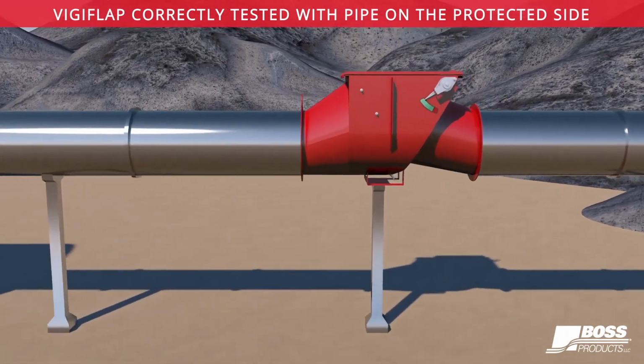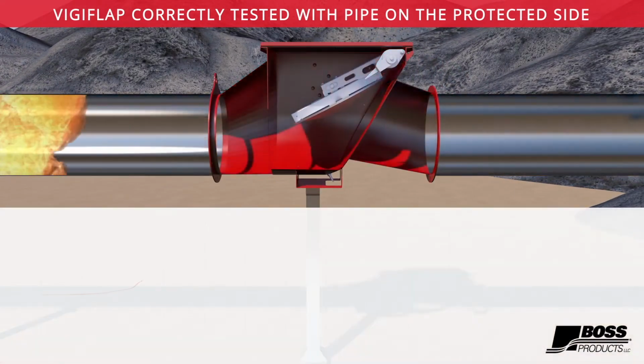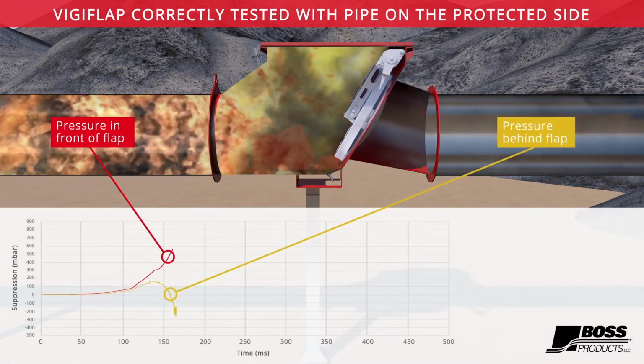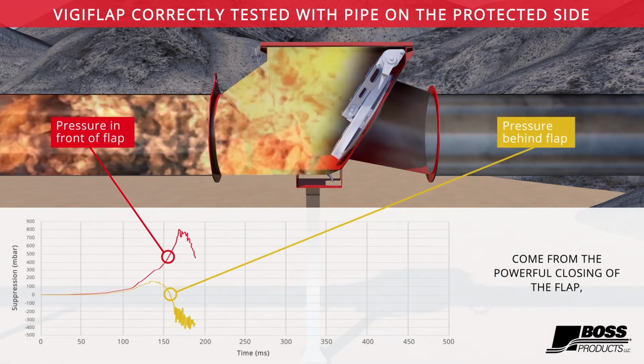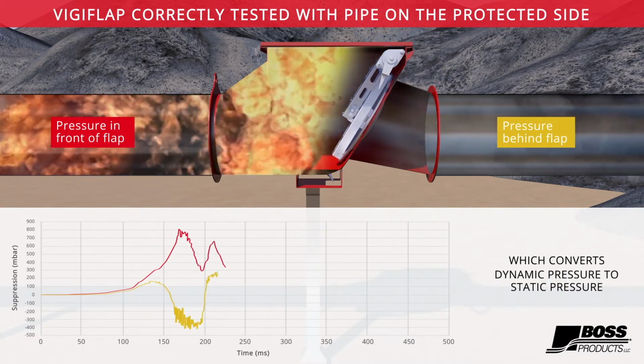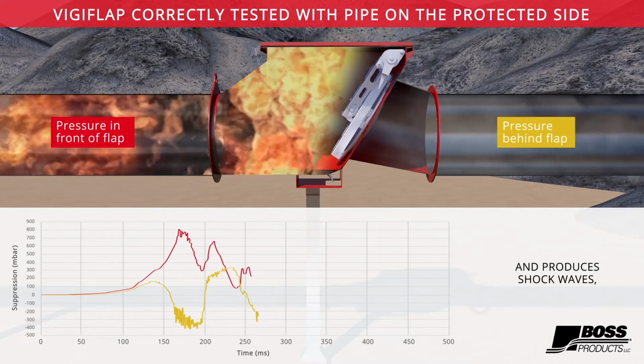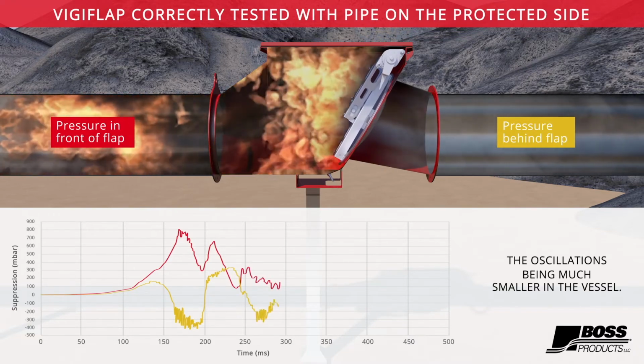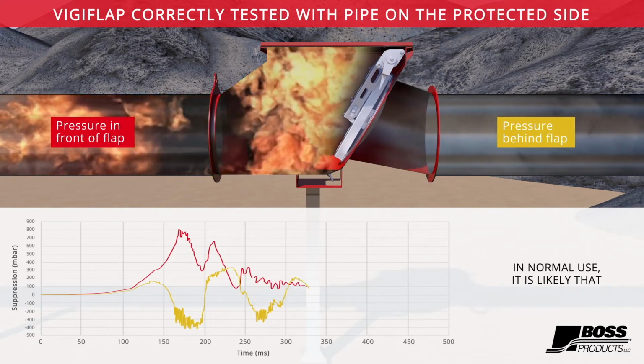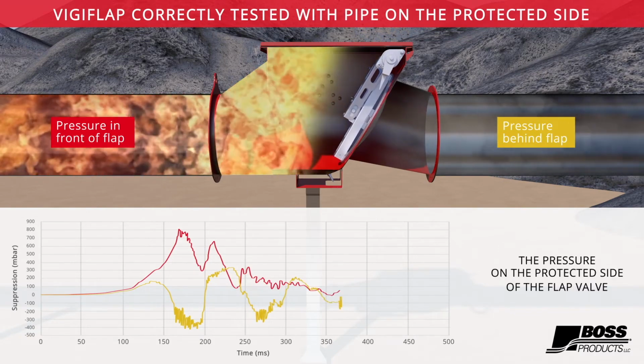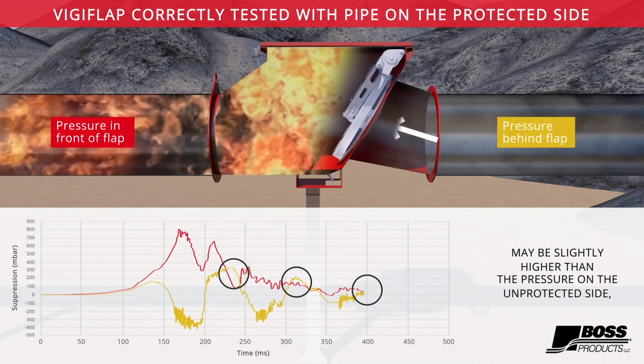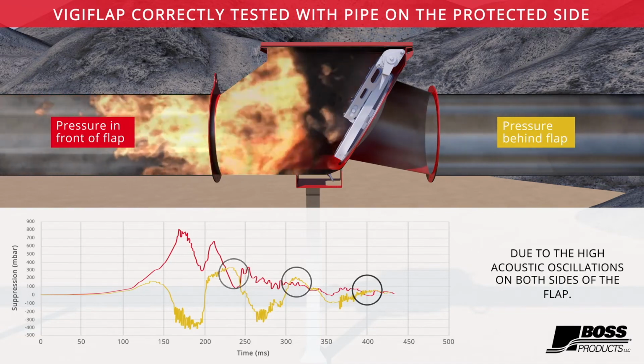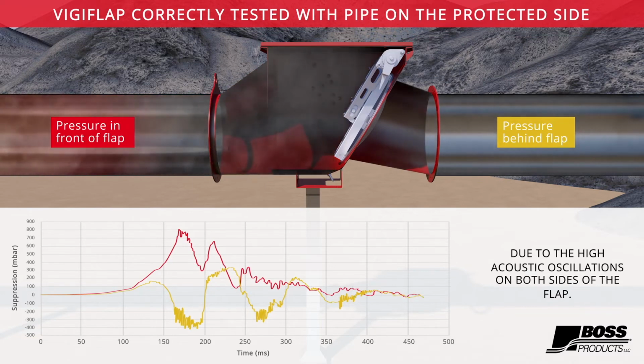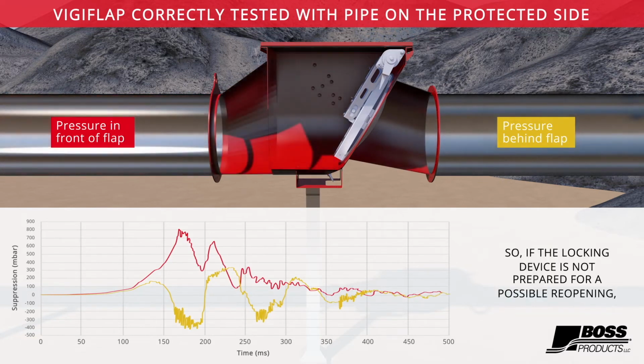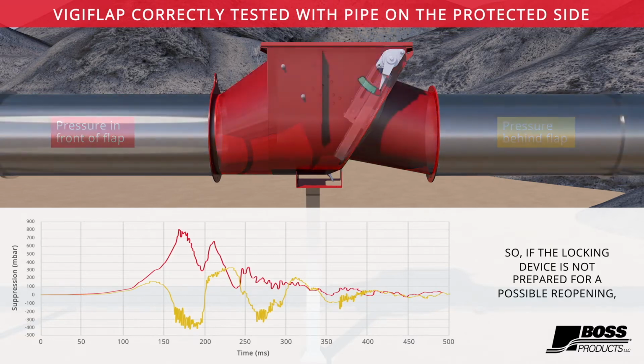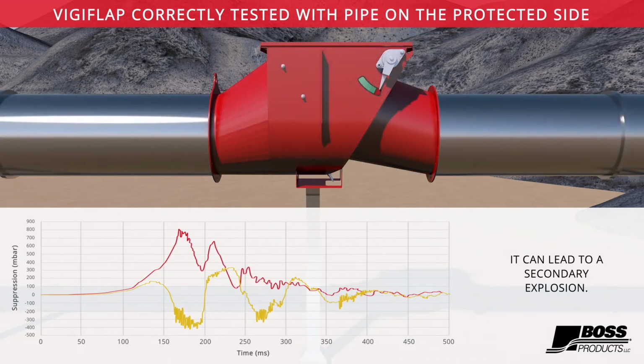Basically how it works is the pressure wave is going to close that flap shut, and the fireball is not going to be able to pass through to the other side of the duct. The very high oscillations in the pipeline come from the powerful closing of the flap, which converts dynamic pressure to static pressure and produces shock waves, the oscillations being much smaller in the vessel. In normal use, it is likely that the pressure on the protected side of the flap valve may briefly be higher than the pressure on the unprotected side, due to the high acoustic oscillations on both sides of the flap. So if the locking device is not prepared for a possible reopening, it can lead to a secondary explosion.